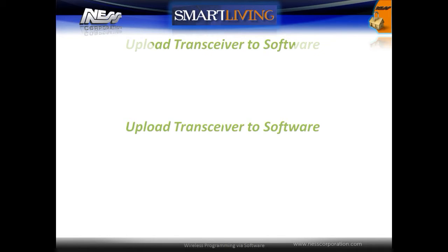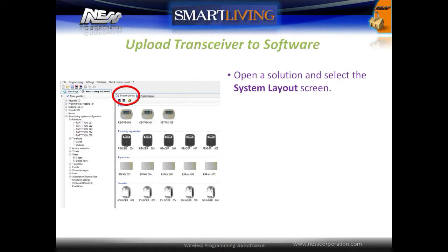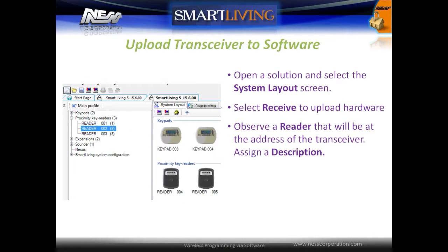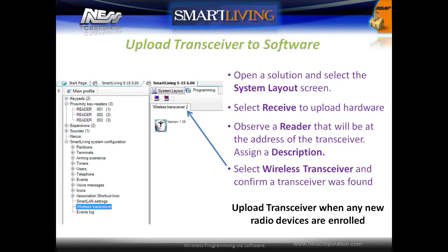To upload the transceiver details into the software, first open a solution and select the system layout screen. Next, select receive to upload the connected hardware. Observe that a reader is uploaded at the address of the transceiver. Assign a description to easily identify the transceiver. Then select wireless transceiver from the system tree and confirm that a transceiver was found. Anytime new devices are enrolled to the transceiver, this tab should be uploaded to the software.